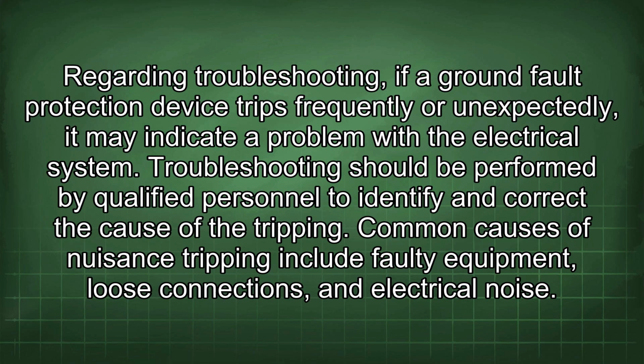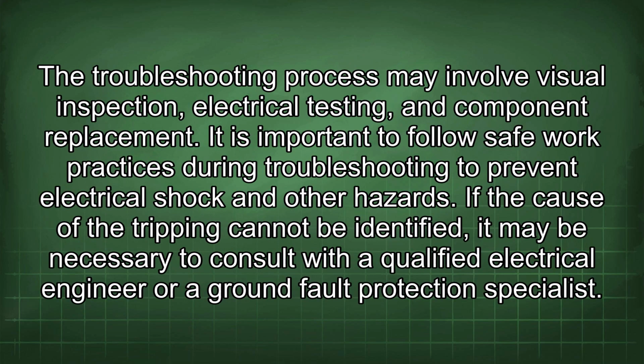Regarding troubleshooting, if a ground fault protection device trips frequently or unexpectedly, it may indicate a problem with the electrical system. Troubleshooting should be performed by qualified personnel to identify and correct the cause of the tripping. Common causes of nuisance tripping include faulty equipment, loose connections, and electrical noise. The troubleshooting process may involve visual inspection, electrical testing, and component replacement. It is important to follow safe work practices during troubleshooting to prevent electrical shock and other hazards. If the cause of the tripping cannot be identified, it may be necessary to consult with a qualified electrical engineer or a ground fault protection specialist.